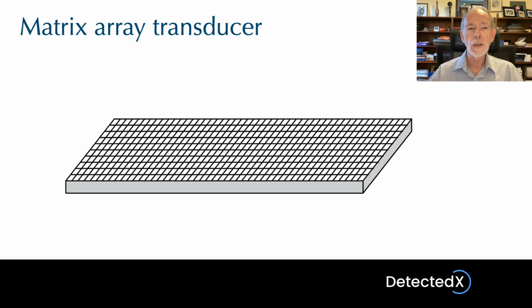The answer is now you're able to use electronic focusing across the width of the transducer as well as along the length of the transducer. And this means that the beam can be focused in both of those dimensions, both within the scan plane and across the thickness dimension of the scan plane, which is often called the slice thickness dimension or the elevation plane. We'll come back to that in the next lecture. So matrix array transducers focus better because they can use electronic focusing across the width. That can be adjusted in depth. It can be dynamic when the machine is receiving, etc. So it has all the same advantages.